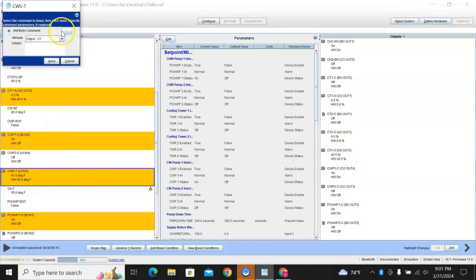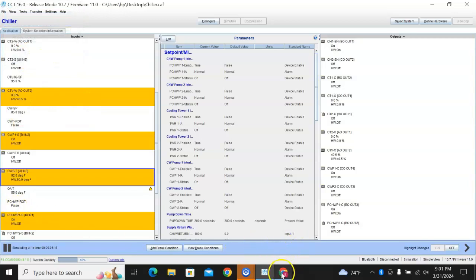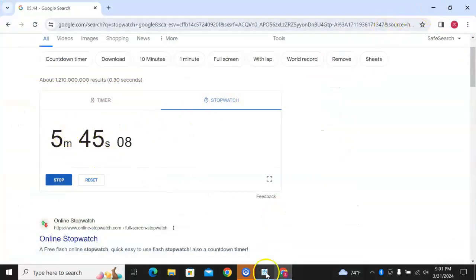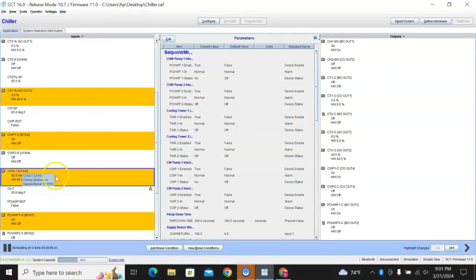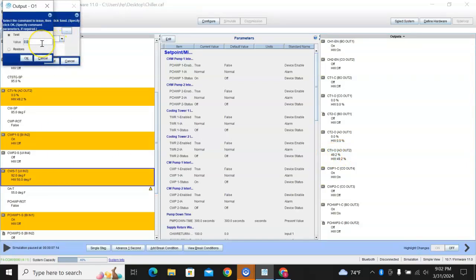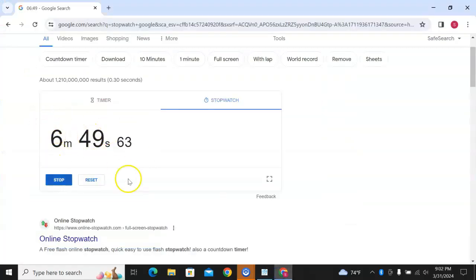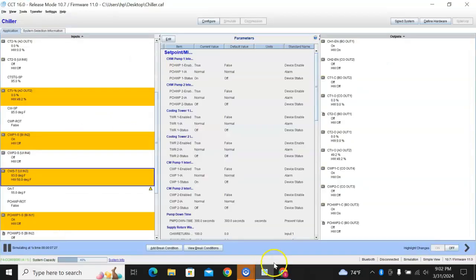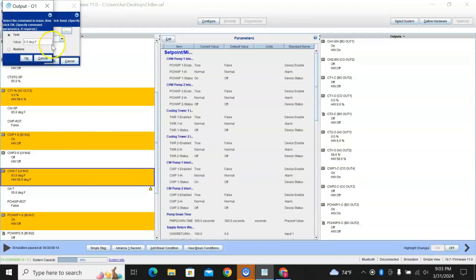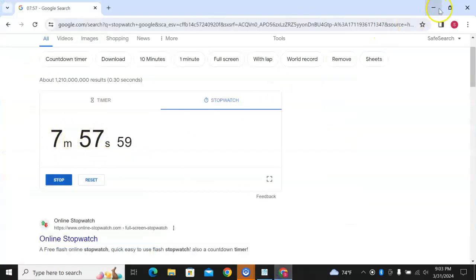Go another degree above. 7 degrees above, 5 minutes 42 seconds. Add another degree here, 93. So I'm at 8 degrees above, almost 7 minutes. Another degree, 94. 9 degrees above, almost 8 minutes.